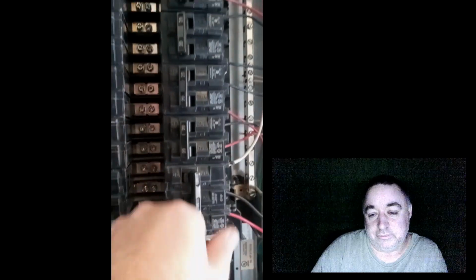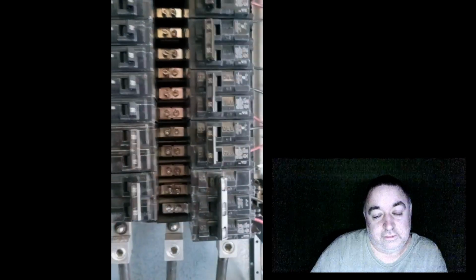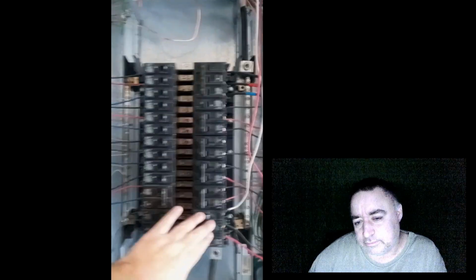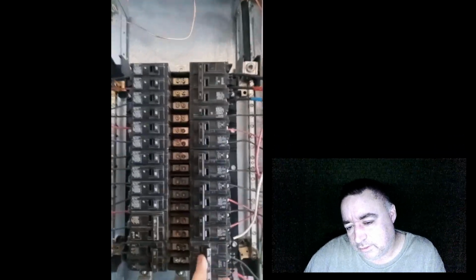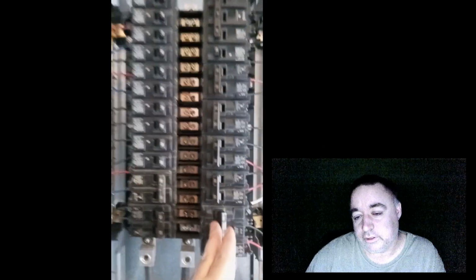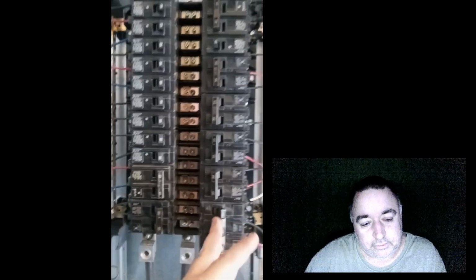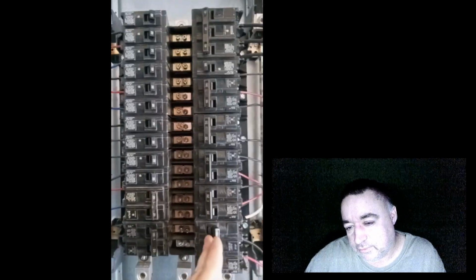That's definitely not good. That's definitely a problem. We're going to tighten that up and see if the meat slicer has power. Right now it has no power. It's showing me power on all 3 legs. Yeah, when you put load on it, you go to put amperage on it, and I'm guessing the connection's not good. I'm going to tighten that up and see what we got. Yeah, I got all 3 of those nice and tight. Put some gloves on too, because I do not like 3-phase. Yeah, I don't like working on a 3-phase panel myself.